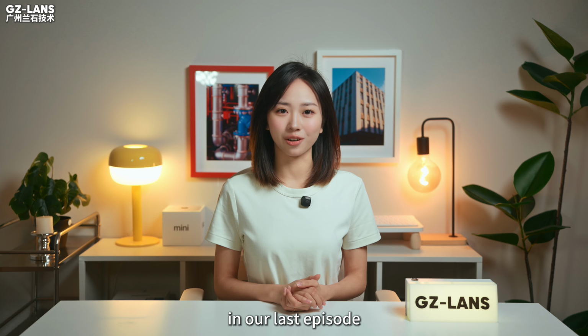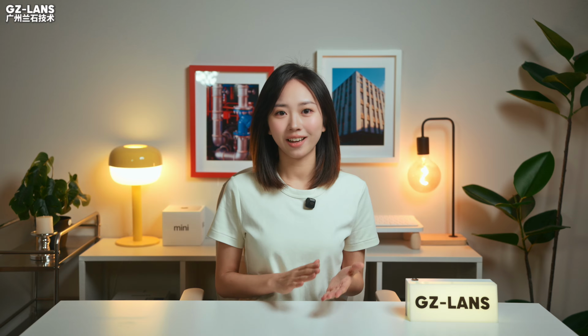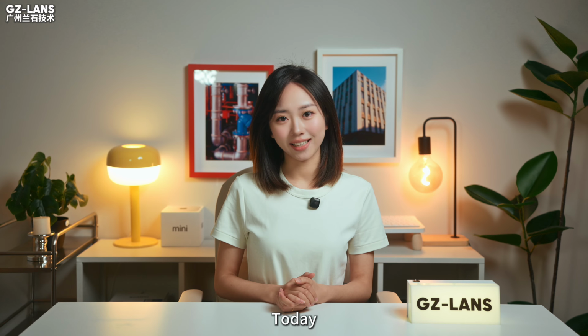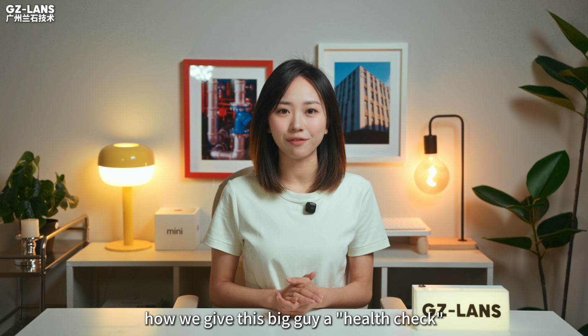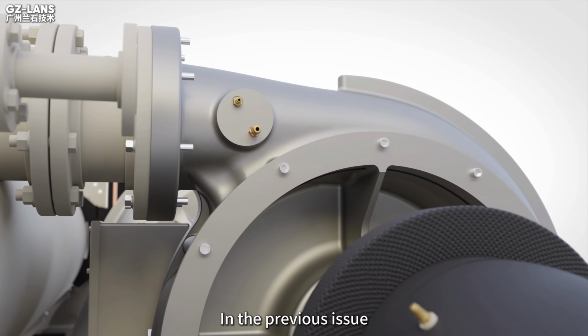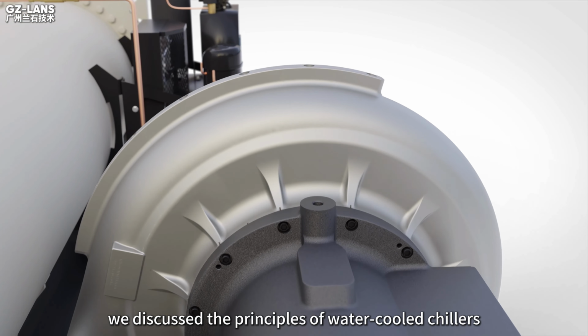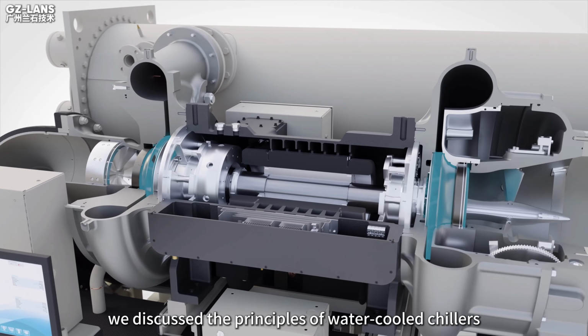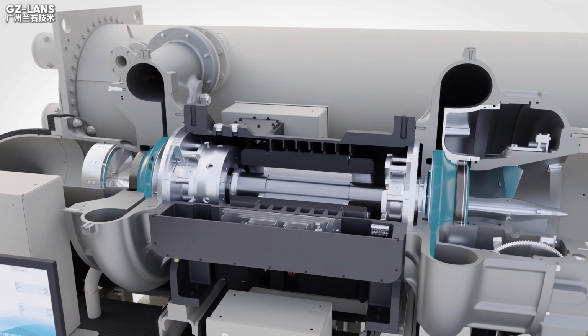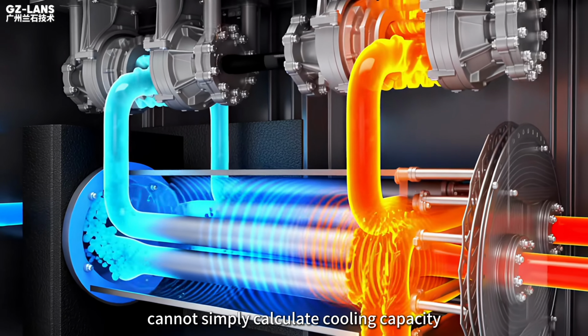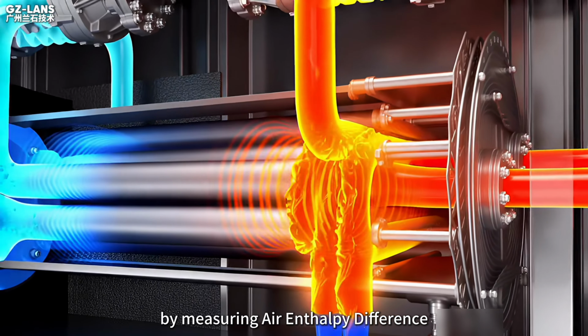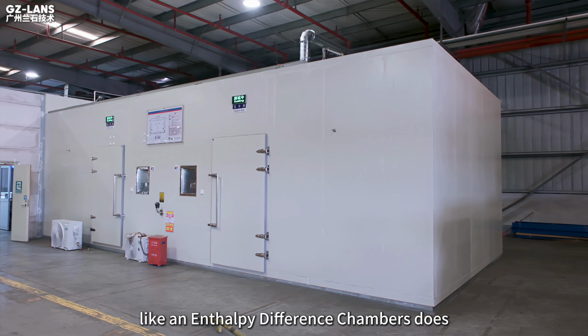In our last episode, we introduced a new friend, the water cooled chiller. Today, let's take a deeper look at how we give this big guy a health check. In the previous issue, we discussed the principles of water cooled chillers. This means that the test lab for such chillers cannot simply calculate cooling capacity by measuring air enthalpy difference like an enthalpy difference chamber does.